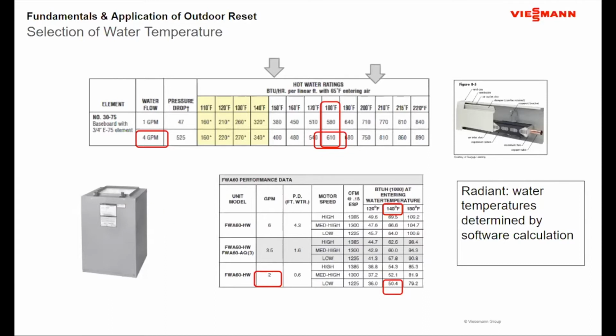But when I look at selecting water temperatures, typically when I'm looking at baseboard or air handlers, a lot of times the selection of the water temperature is based on the preference of the engineer or designer of where they want that water temperature to be.